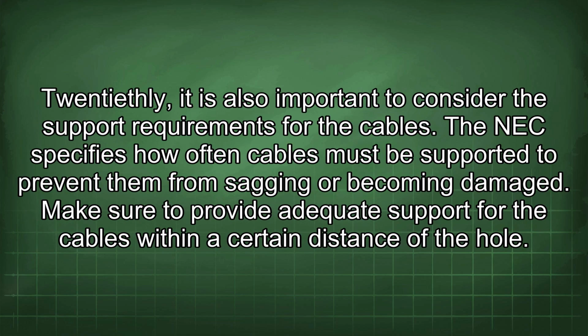20thly, it is also important to consider the support requirements for the cables. The NEC specifies how often cables must be supported to prevent them from sagging or becoming damaged. Make sure to provide adequate support for the cables within a certain distance of the hole.